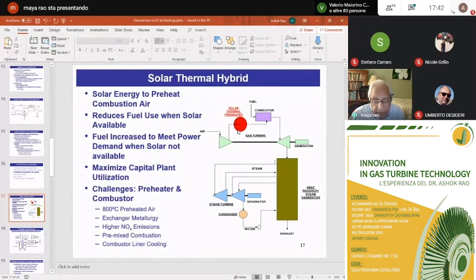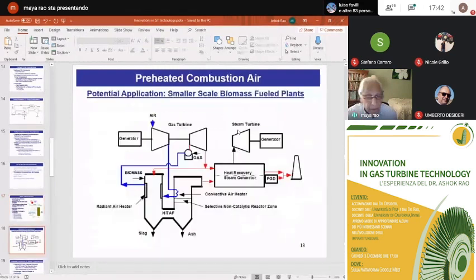Now, a similar cycle has also been worked on. Instead of using solar energy for preheating the air going to the combustor, here we use a biomass combustor. You have the compressor, and the compressor discharge goes into a heater, a furnace, where you're burning biomass and transferring the heat. The hot air then enters the combustor of the gas turbine and expands.